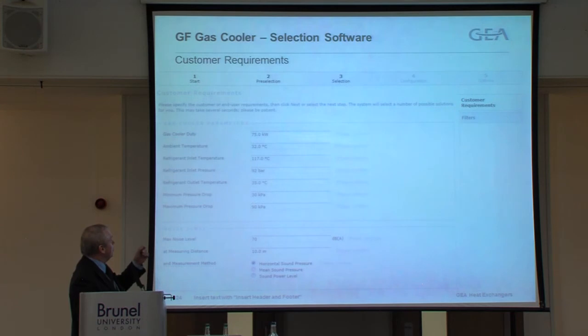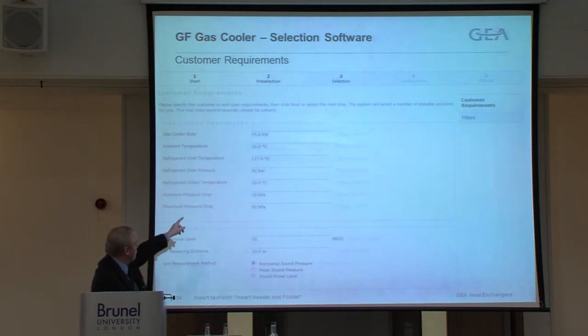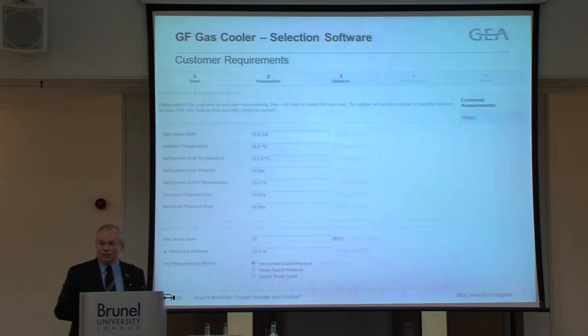Fairly simple, all you have to do is put in kilowatt capacity and the ambient. There is an option to put in the noise level, it's not displayed on this particular slide. Then the gas inlet temperature and the pressure, your desired outlet temperature, and then the minimum and the maximum pressure drop that you want through the coil. This is so that you can design for when you go from transcritical to subcritical, you minimise the pressure drop through the coil. Press the button.